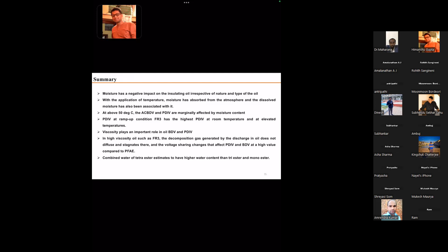Partial discharge inception voltage at ramp-up condition, FR3 has the highest PDIV at room temperature and at elevated temperature. Viscosity plays an important role in oil BDV and partial discharge inception voltage. In high viscosity oils such as FR3, the decomposition gas generated by the discharge in the oil does not diffuse and stagnates there. And the voltage sharing changes that affect the PDIV and BDV to a higher value compared to the others. Combined water of tetraester is estimated to be higher than triester and monoester. These are the summary of what we have carried out in this research.